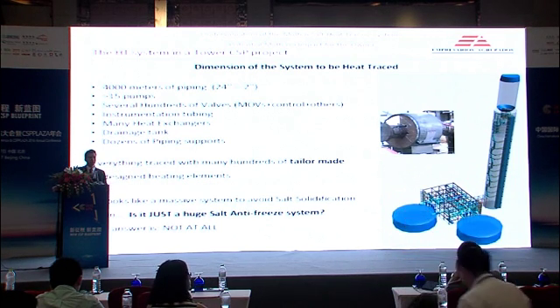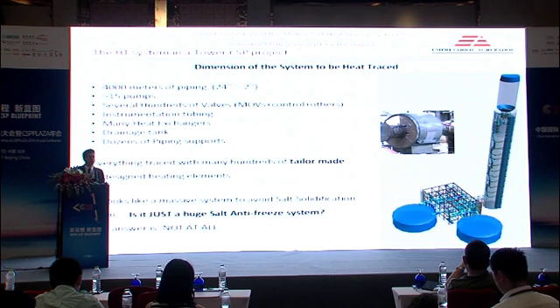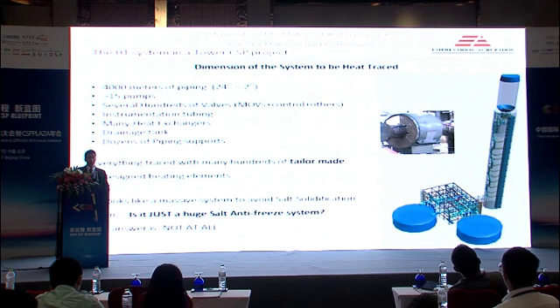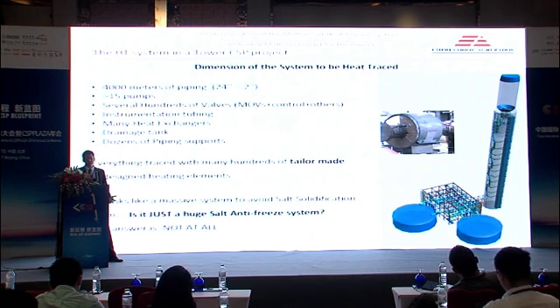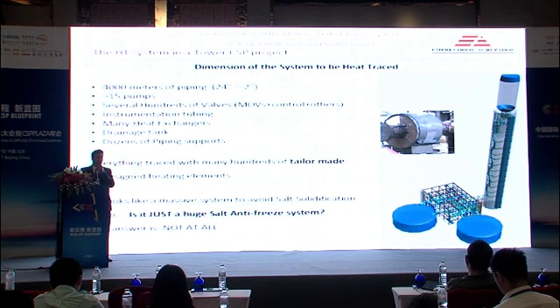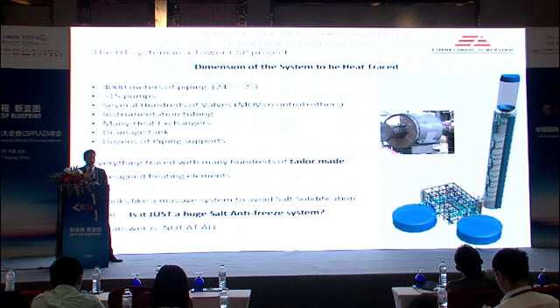We easily accumulate 4,000 meters of piping of very different sizes, all of which needs to be heat traced, along with a lot of pumps, hundreds of valves, heat exchangers, instrumentation, the drainage tank down there, and even the pipe supports of the molten salt pipe system, which must be heat traced at certain points due to stress issues across the range of temperatures.